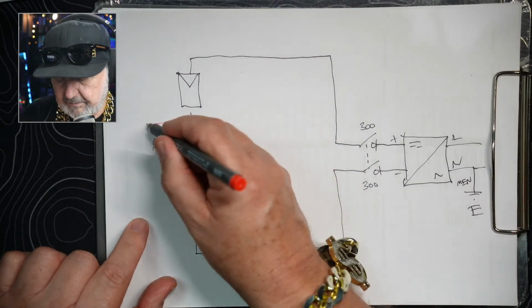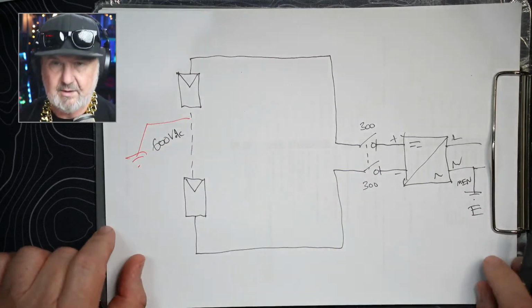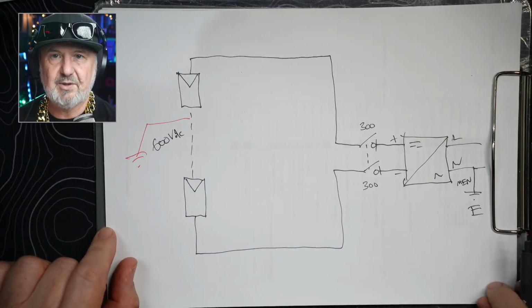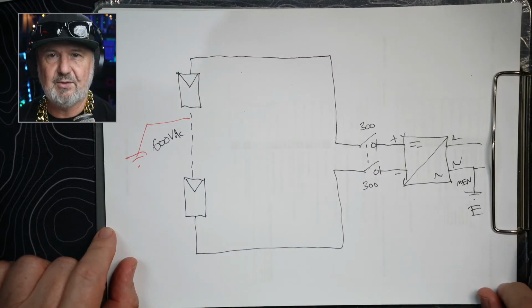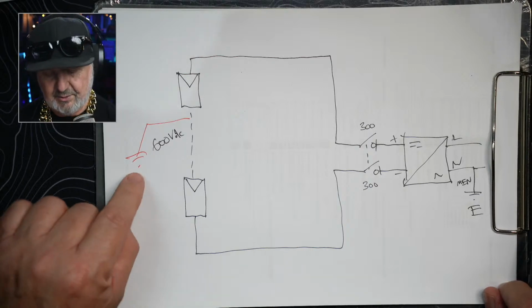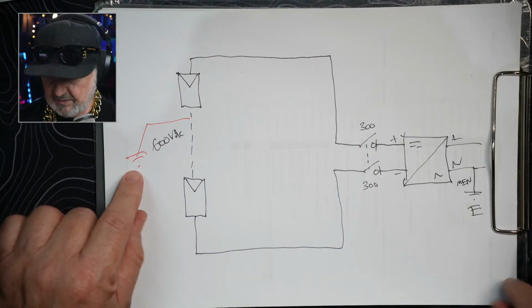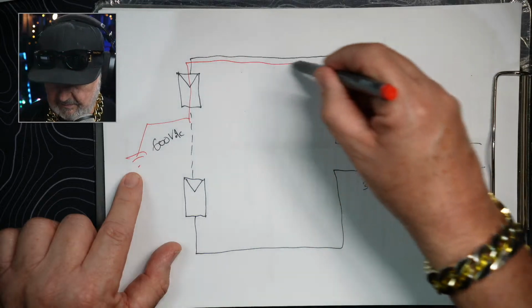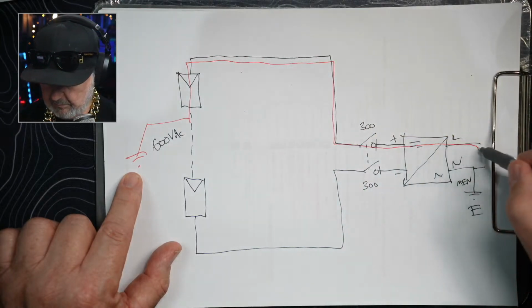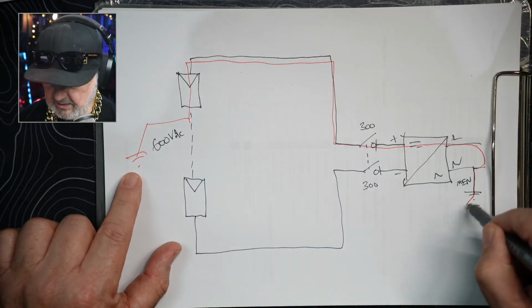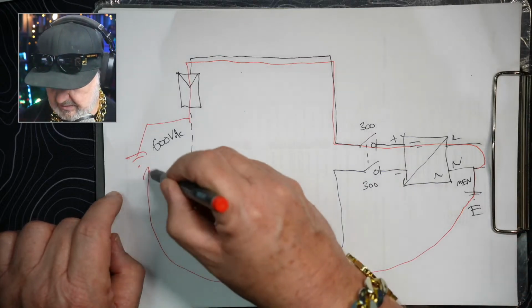But as soon as you have a non-separated inverter and you have a fault, say you have an earth fault, right? So a nice Australian possum made its way to New Zealand, chewed through some cables on the roof, shorted out to the array frame. You've now got a fault path that looks like this. Through the transformer, through the MEN, and back to here.